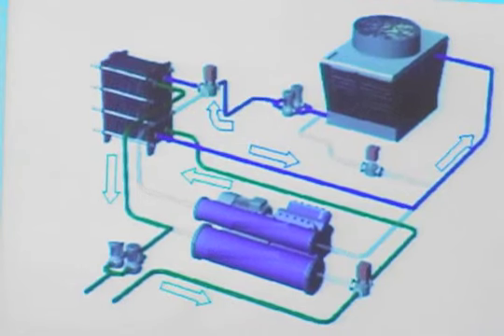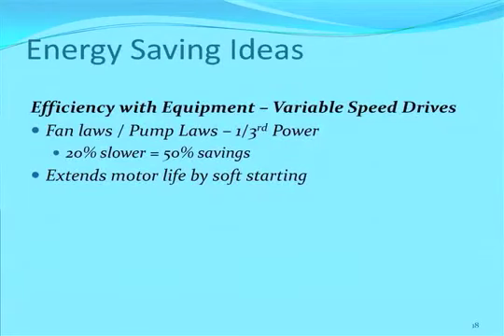I didn't come up with a slide for the closed loop fluid cooler, but basically to do that you're eliminating the plate and frame and going directly to the fluid cooler with the chilled water and then having the condenser water just circulate internally here. Variable speed drives, motors abide by fan laws or pump laws, affinity laws, which is a 1/3 power law, meaning if you slow down the motor a little bit, you can save a lot in the power department. It also has the added benefit of extending the motor life because it's not an abrupt on-off.